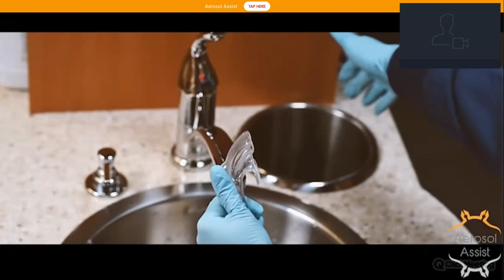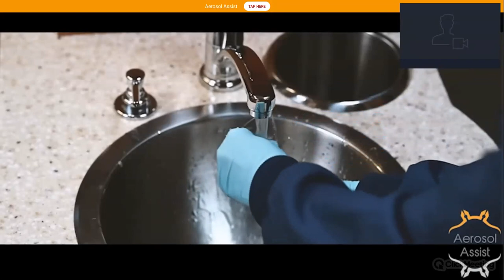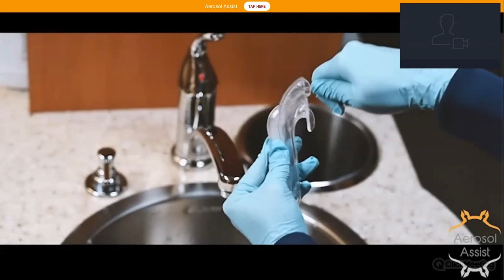After each use, the saliva ejector is discarded. The aerosol assist is then rinsed internally and externally to flush out any debris. The HVE port has two internal channels that can be cleaned with a standard brush. The aerosol port has access to those same channels and should be cleaned as well. After rinsing, they can be ultrasonically cleaned in an enzymatic bath and then placed in standard sterilization pouches.